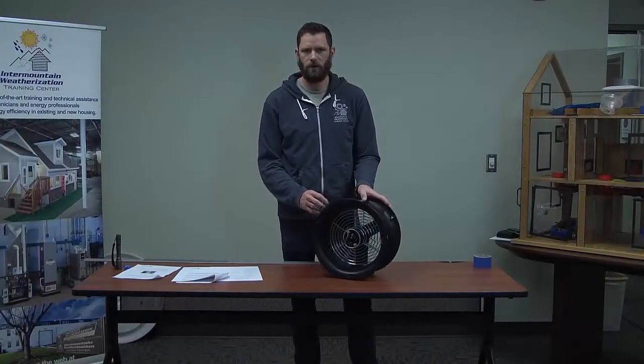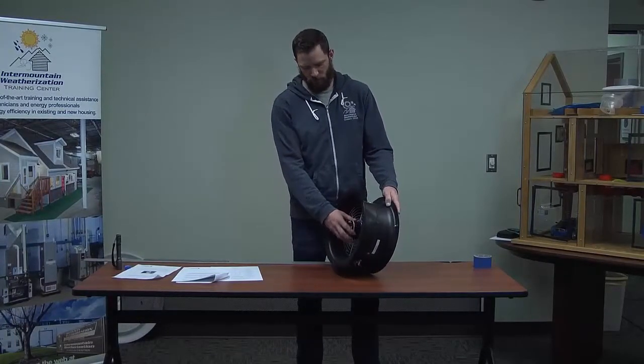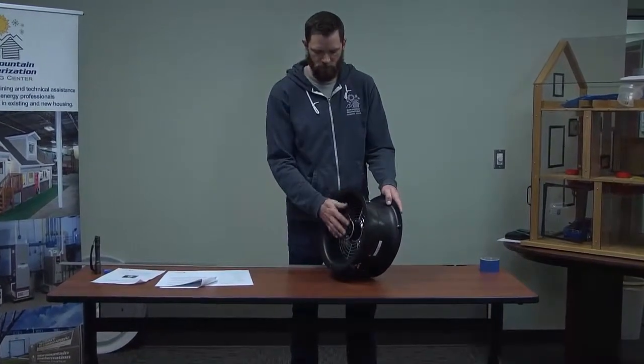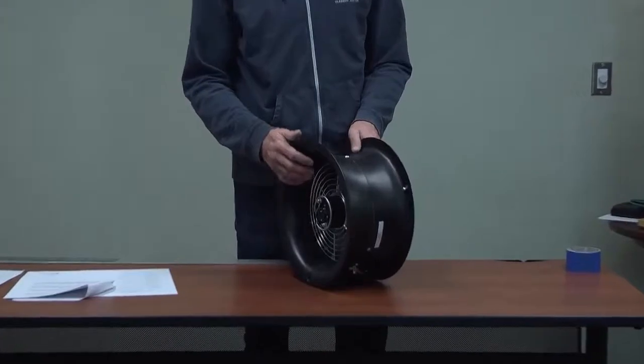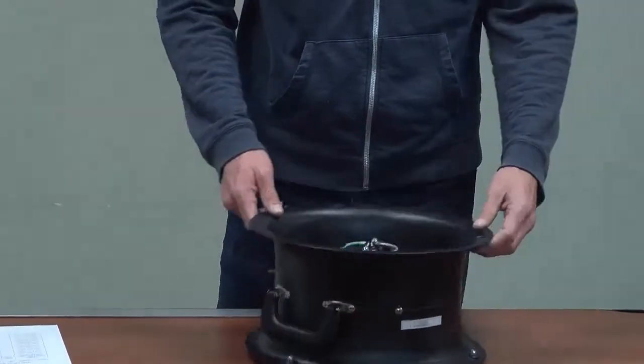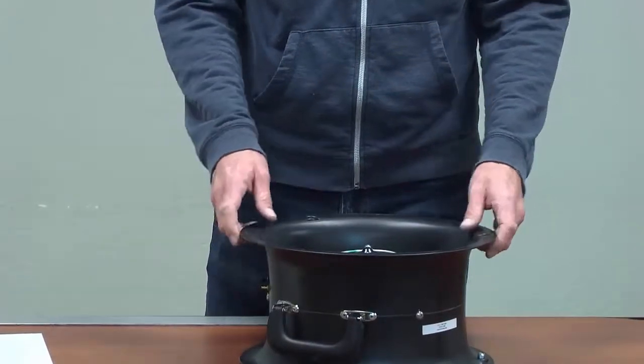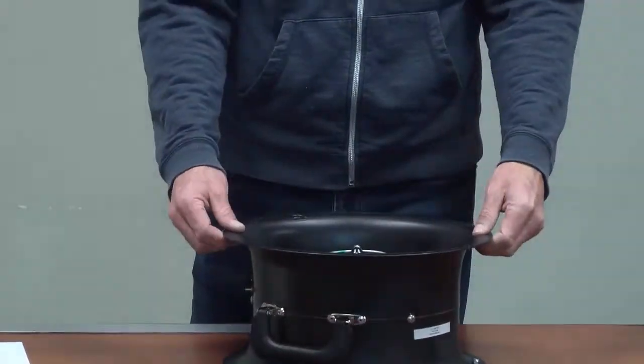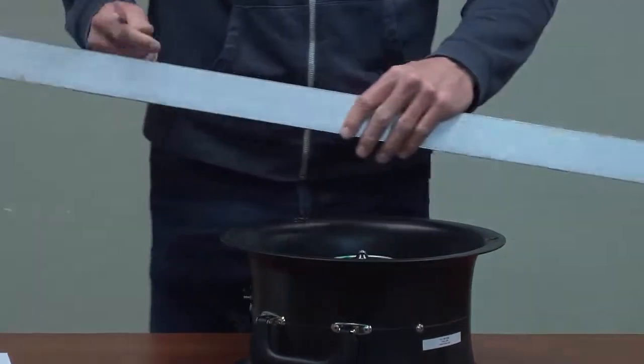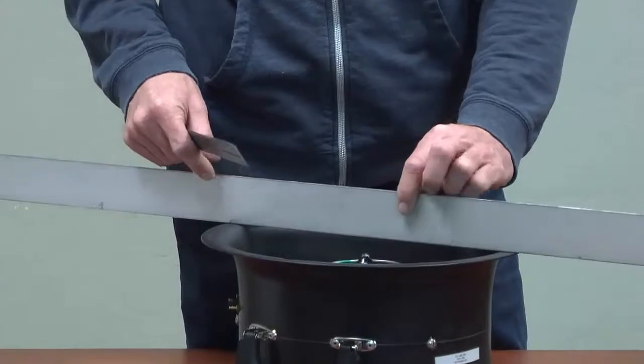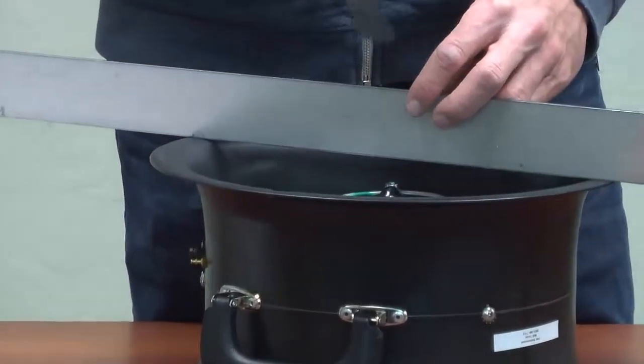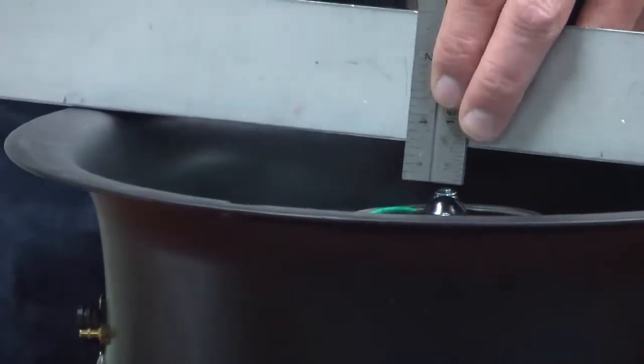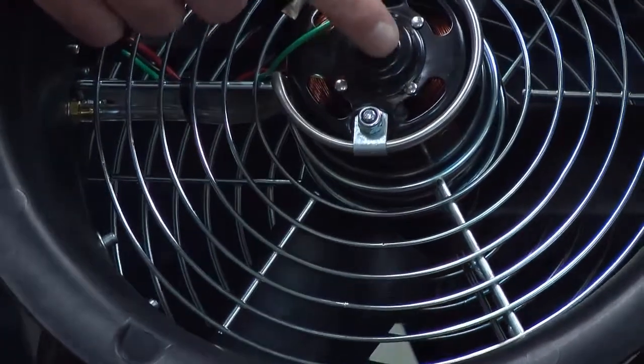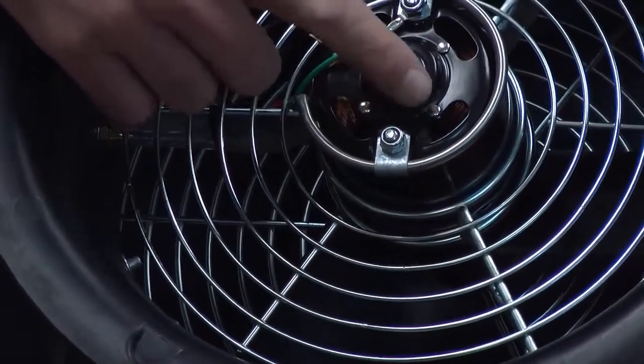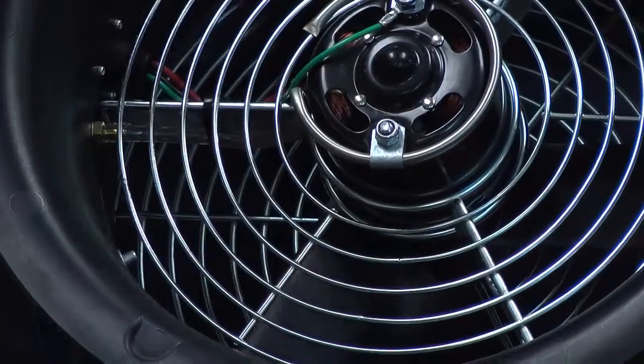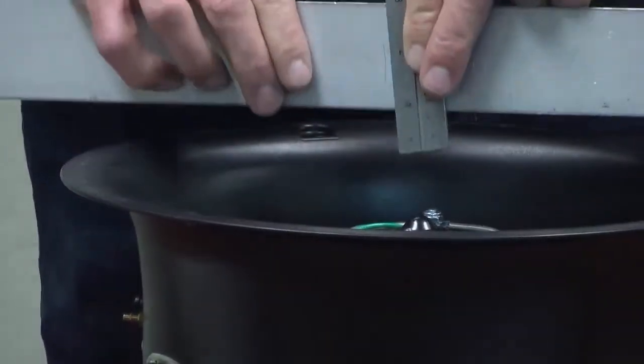Alright, so the next test that we're going to do is check the positioning of the flow sensor in relationship to the housing to make sure it's in the right spot so that it's getting a proper reading. You want to lay it on the back or on its side with the flow sensor facing up. You're going to take a straight edge laid across the housing. And if you take a ruler, it's important for me to point out, there's a little nub right here on the back of the motor. That's what you're going to be measuring off of. That's what they want you to gauge off of.